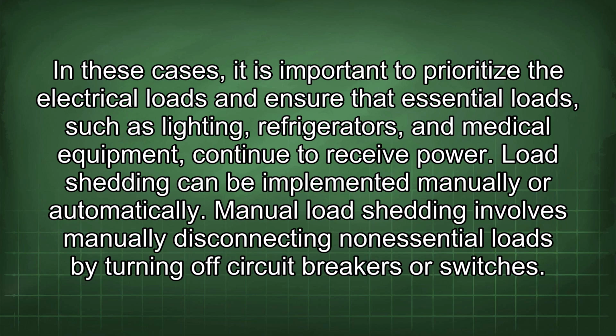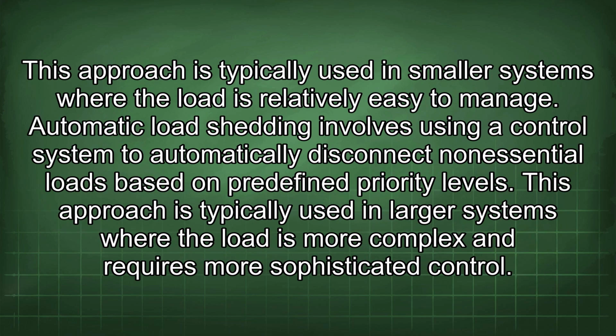Load shedding can be implemented manually or automatically. Manual load shedding involves manually disconnecting non-essential loads by turning off circuit breakers or switches. This approach is typically used in smaller systems where the load is relatively easy to manage. Automatic load shedding involves using a control system to automatically disconnect non-essential loads based on predefined priority levels. This approach is typically used in larger systems where the load is more complex and requires more sophisticated control.